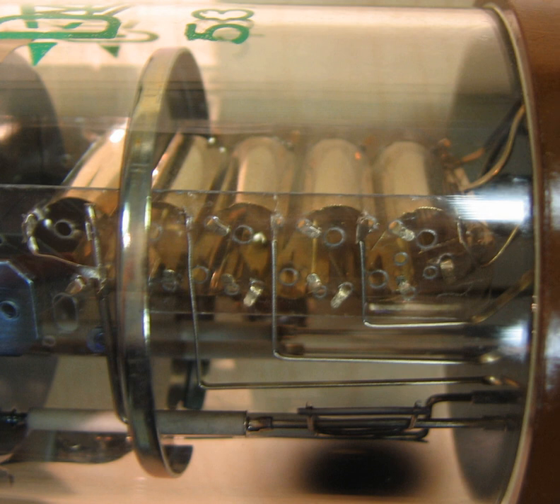The divider design, which influences frequency response or rise time, can be selected to suit varying applications. Some instruments that use photomultipliers have provisions to vary the anode voltage to control the gain of the system. While powered-energized, photomultipliers must be shielded from ambient light to prevent their destruction through overexcitation. In some applications this protection is accomplished mechanically by electrical interlocks or shutters that protect the tube when the photomultiplier compartment is opened. Another option is to add overcurrent protection in the external circuit, so that when the measured anode current exceeds a safe limit, the high voltage is reduced.